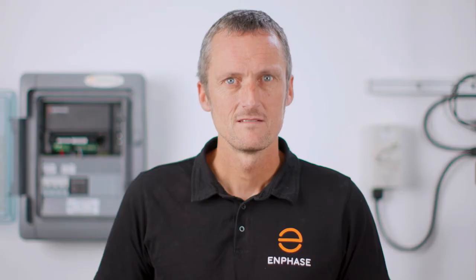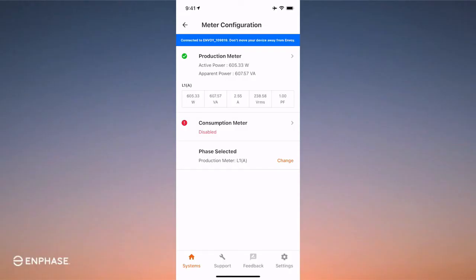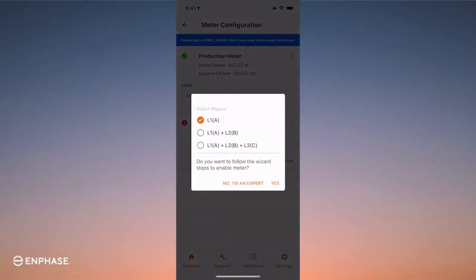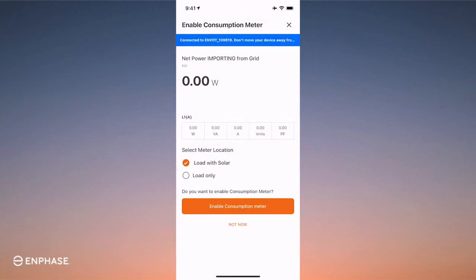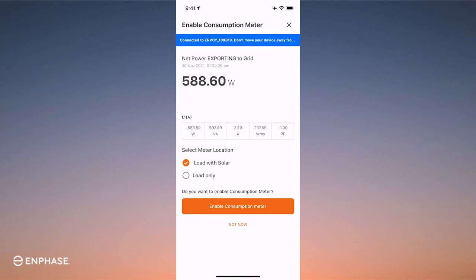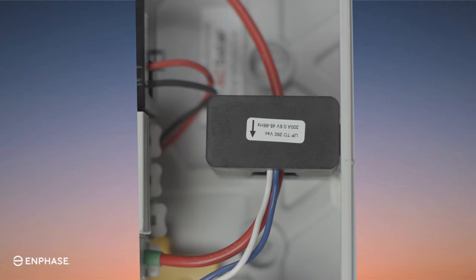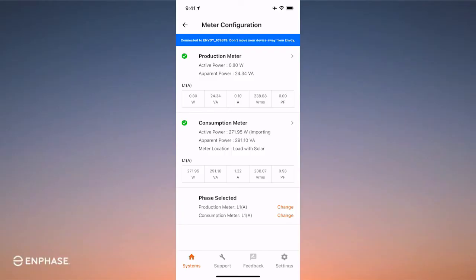Now let's get into consumption CTs — these are trickier so pay close attention. Select 'No, I'm an expert.' You may choose to select the wizard for additional step-by-step instructions. For consumption type, be sure to select the correct option. 'Load with solar' will be your choice for your installations, as the consumption CT will be positioned line side of the main switchboard so it can measure the load and also measure the exported solar value. Ensure the CT arrow faces away from the supply towards the switchboard. Be sure to confirm your readings — I recommend testing the current with a multimeter and also confirming the readings with the app.